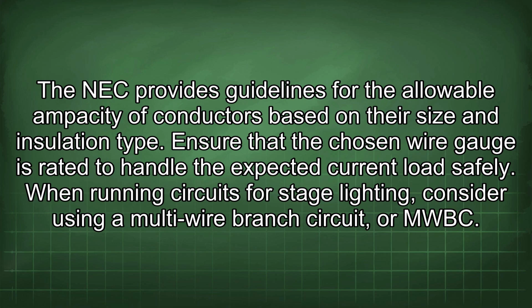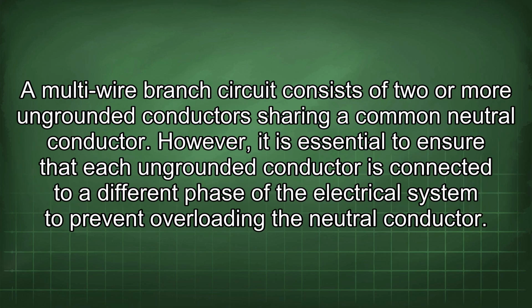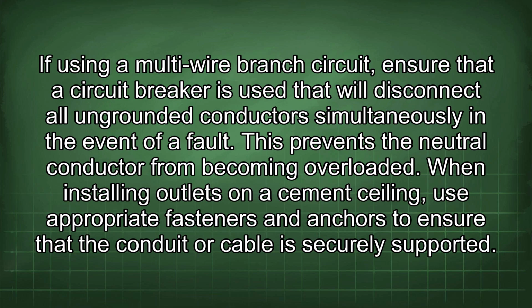When running circuits for stage lighting, consider using a multi-wire branch circuit, or MWBC. A multi-wire branch circuit consists of two or more ungrounded conductors sharing a common neutral conductor. However, it is essential to ensure that each ungrounded conductor is connected to a different phase of the electrical system to prevent overloading the neutral conductor. If using a multi-wire branch circuit, ensure that a circuit breaker is used that will disconnect all ungrounded conductors simultaneously in the event of a fault. This prevents the neutral conductor from becoming overloaded.